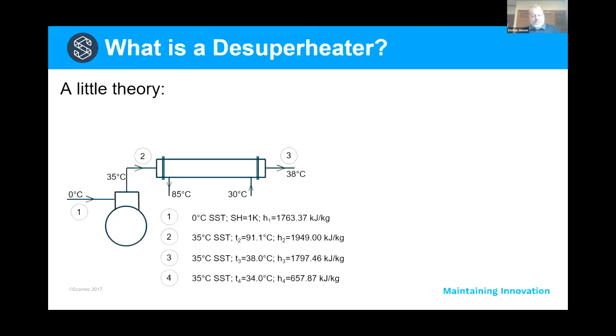First of all, I might dwell a little on what a desuperheater is. In this little diagram, the round thing with a top hat is a compressor, and the rectangular thing is a desuperheater. I've shown it as a cylinder tube, but it doesn't have to be that way. The numbers 1, 2, 3, 4 represent the condition of the refrigerant. Inlet condition to the compressor is number 1, saturated suction temperature 0 degrees, and the enthalpy is shown. Once the gas has been compressed, it reaches condition 2, where the temperature has gone up to 91 degrees and the enthalpy has increased.